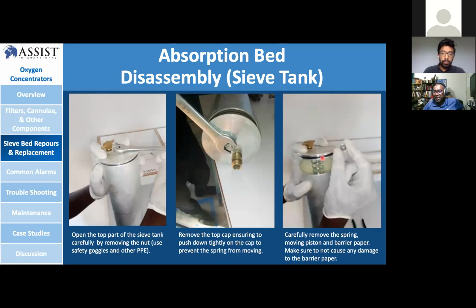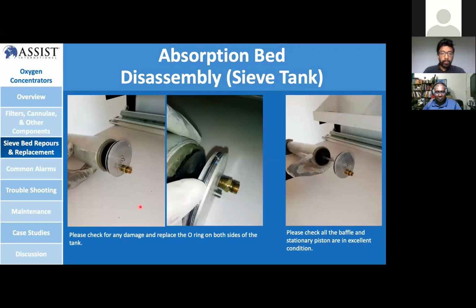So carefully remove the spring, and there's a moving piston there, and a barrier paper. Be careful with the barrier paper, because you want to reuse it. So make sure that you open it carefully and remove it slowly. Then at the bottom part, check for any damage and replace the O-ring on both sides of the tank. Please check the baffle part at the bottom, and that the stationary piston is in excellent condition. If everything is good, you can start to fill up with the zeolite. But make sure everything is in good condition before you start to assemble with the new zeolite.